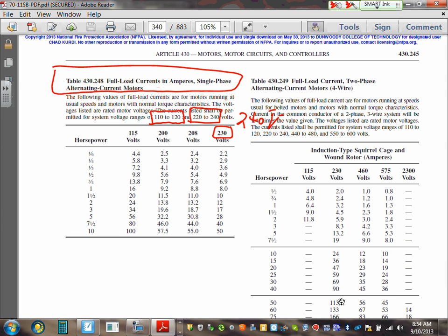Okay, so for a 240 volt, we go here, and it was 3 horsepower. Here's my horsepower. Here's my voltage, because 230 goes with 240. What's the full load current? This is the full load current, 17. That's how you use this table. Can I have thumbs up, Chad? We know how to use this table. Cool? Straightforward. If that was a 10 horsepower, what would the full load current be? 50. If that was 1/6 of a horsepower, what would the full load current be?